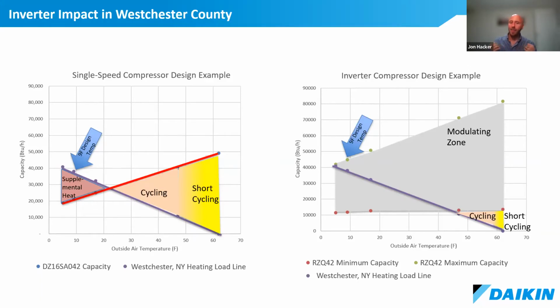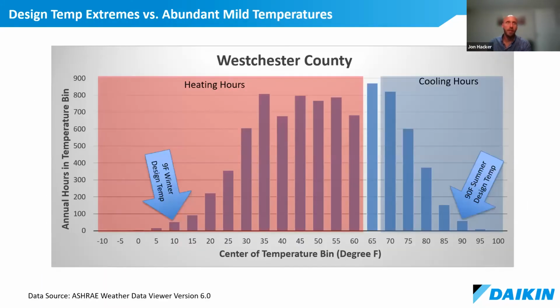Shifting over to the right-hand side of the slide, we're showing the same heating load line in purple. We're showing the same product that we showed before, but the modulating zone. And basically we're bringing all these concepts together, right? With the inverter, we can now provide 100% of the heating that this home would need because the inverter allows the delivery of more heat when it's cold outside. And we're also not cycling starting around 23 or 24 degrees Fahrenheit, but instead we're modulating and operating more efficiently all the way up to maybe 46 degrees Fahrenheit outside, at which point the load drops below the minimum for this product, and we would have some cycling. And again, we'll have some healthy cycling, maybe up to around 58 degrees Fahrenheit. And we'll have some short period of time, maybe between 58 and 62 degrees, where we'll have some short cycling. So over the season, the equipment is going to operate much more efficiently.